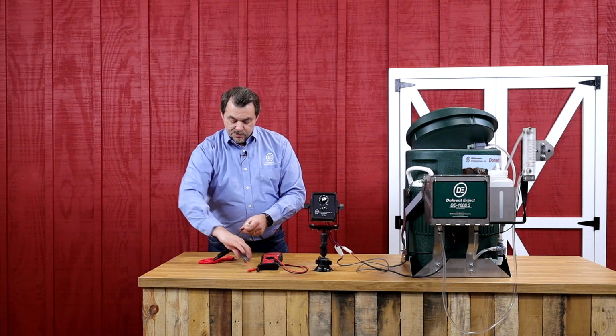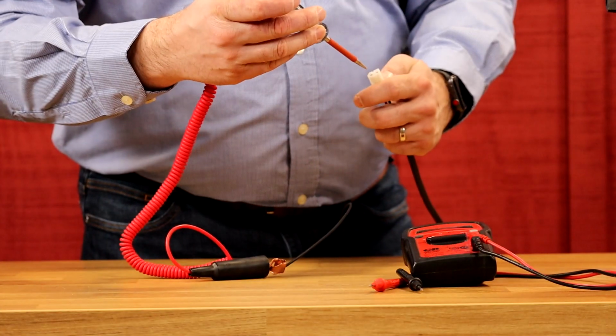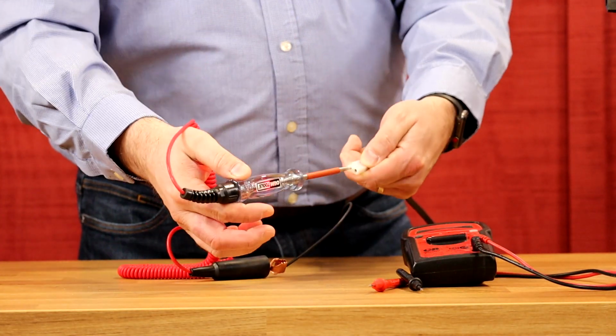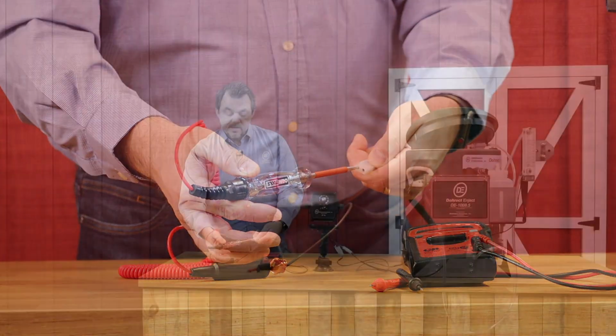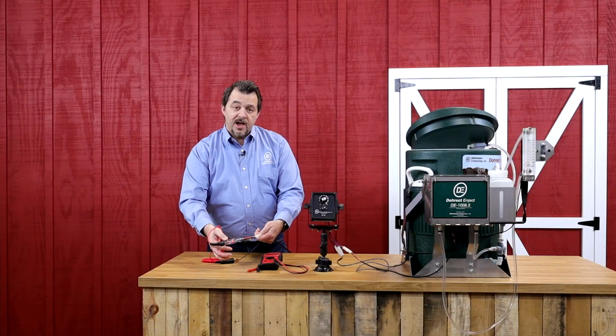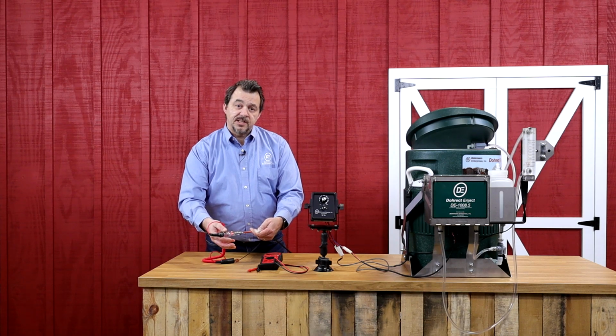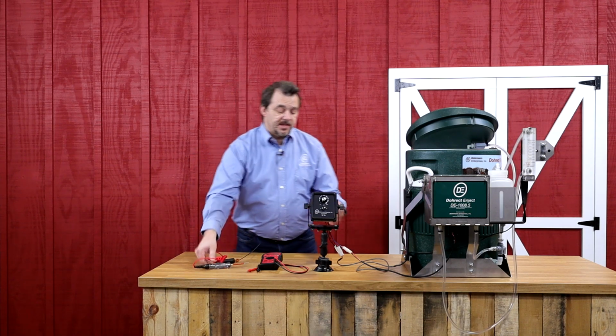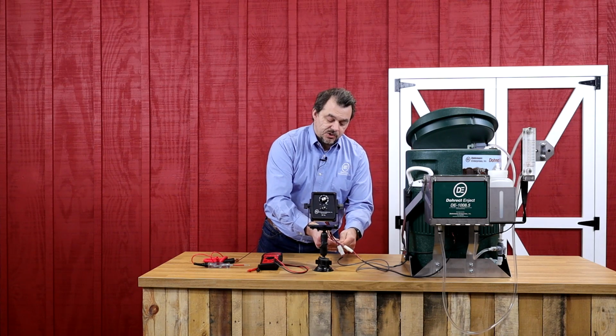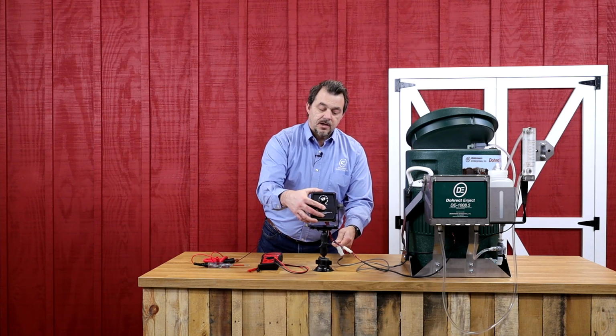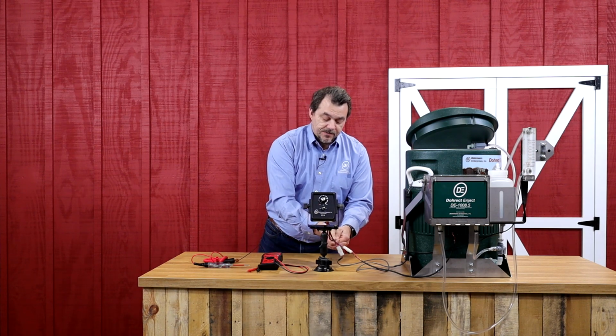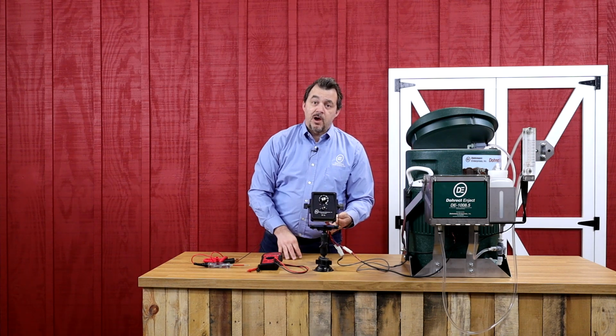And in this example, you'll see that we have power. So it shows that we have power on the hotline and we're grounded somewhere else. But this only tells us that we have power, because if we take this and plug it back into the control, we still don't have power. And the reason for that is it's a bad ground.